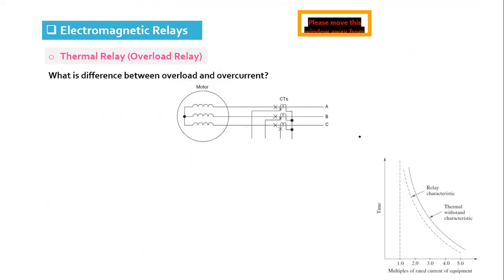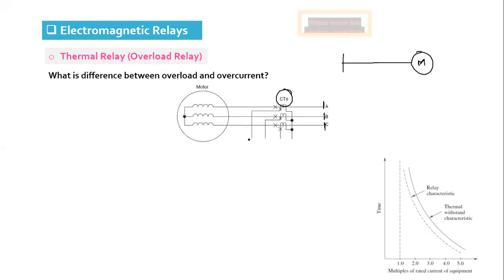So let us now discuss the relay. To understand it, consider this is a motor, the same diagram, a three phase motor connected with three different phases, let's say A, B, C. These are the currents fed to the relay. Here the relay will be, this relay is a thermal relay. Whatever current the motor draws from the primary, accordingly the secondary current will be reflected in the relay coil. These are the motor windings of all three phases, connected with some mechanical load.